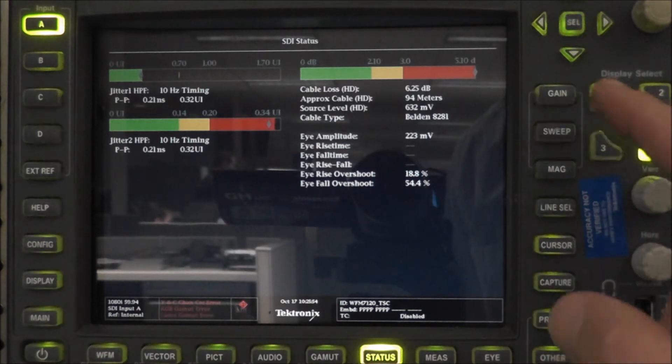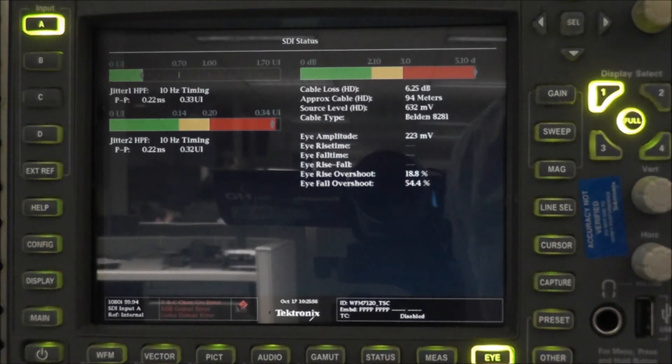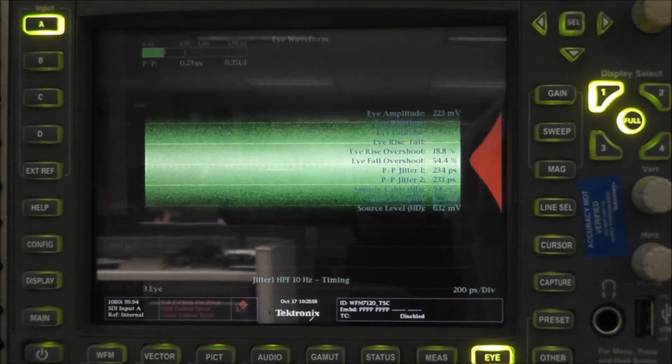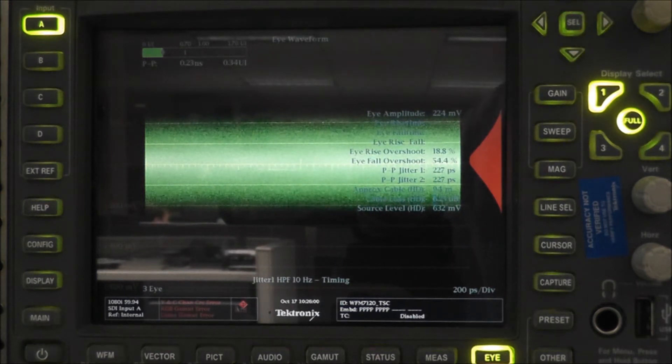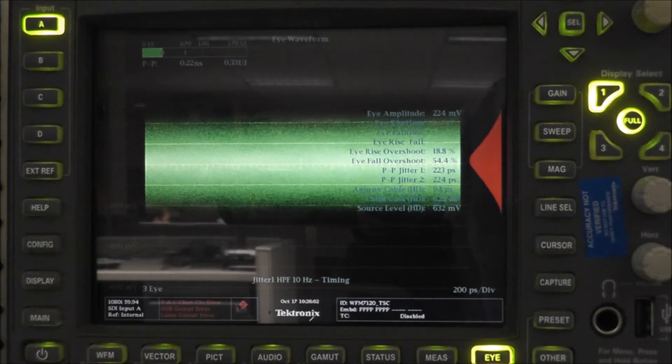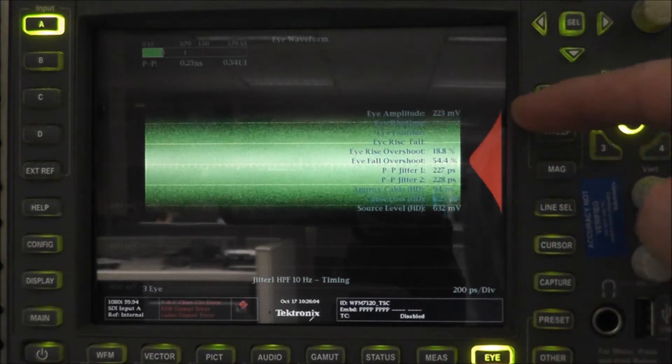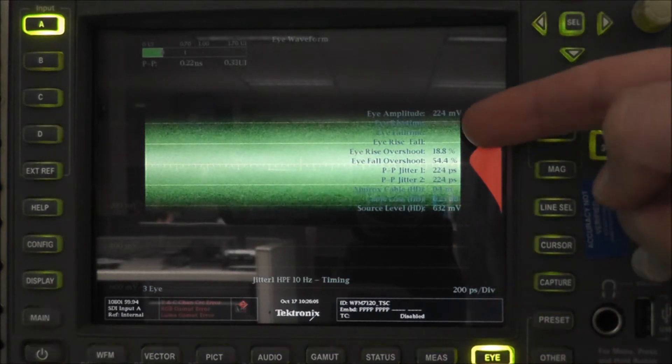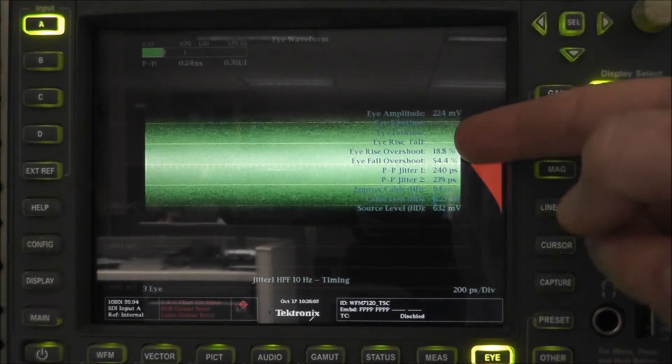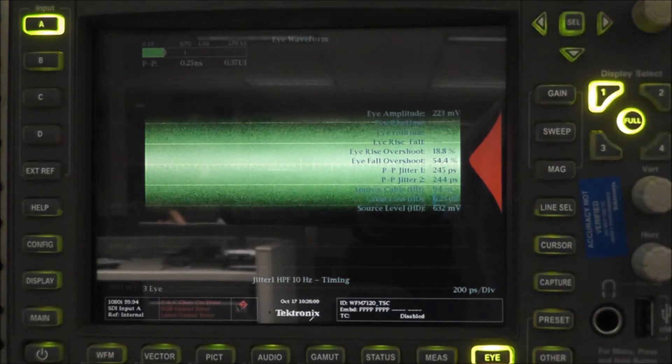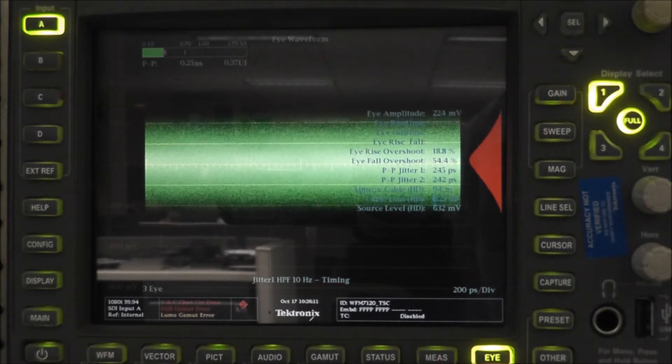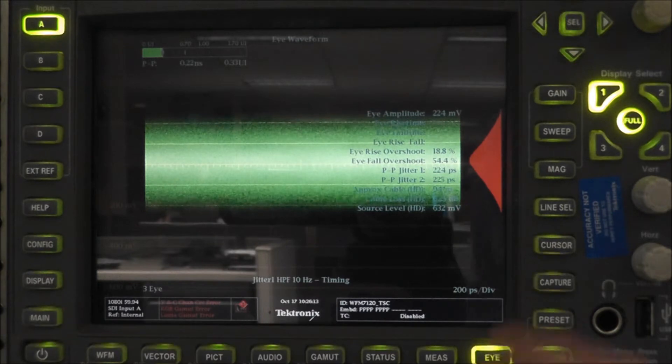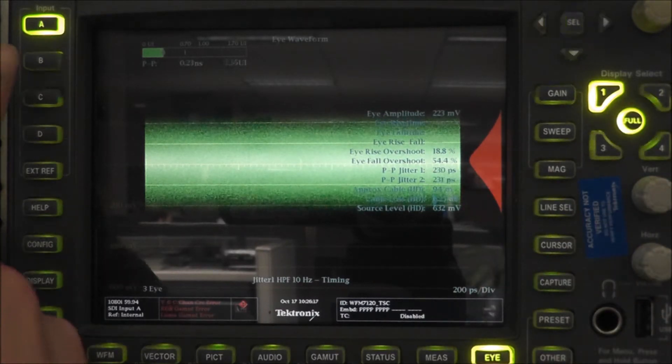It shows us some cable loss, but no rise-fall time. If we go to the eye pattern, which is virtually a blur, we can see that it is not able to properly calculate those eye measurements, those rise-fall times, just simply because it cannot find the rising edge and falling edge.